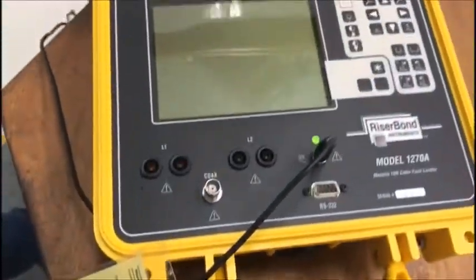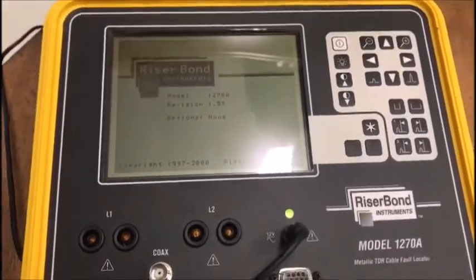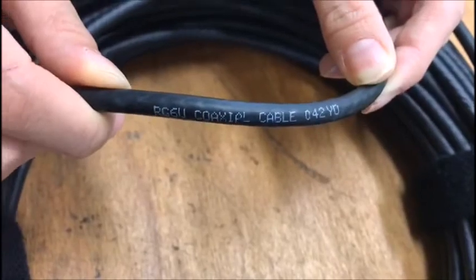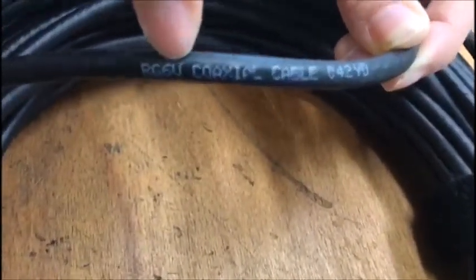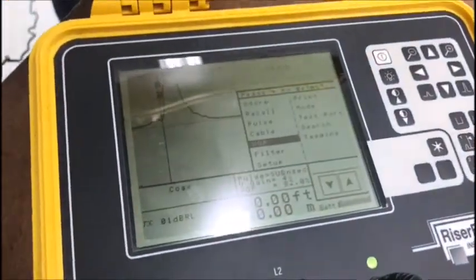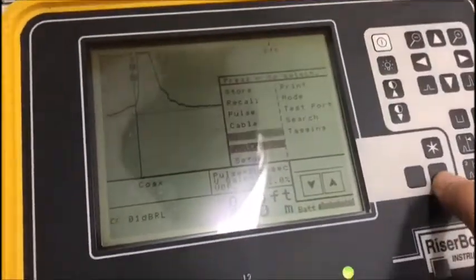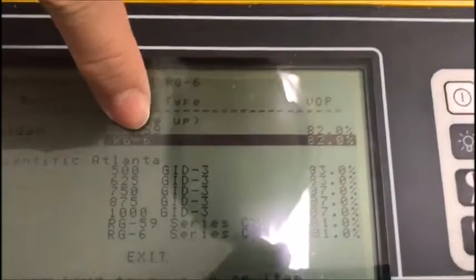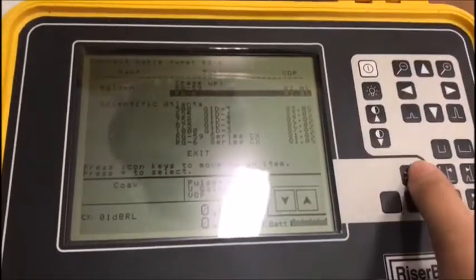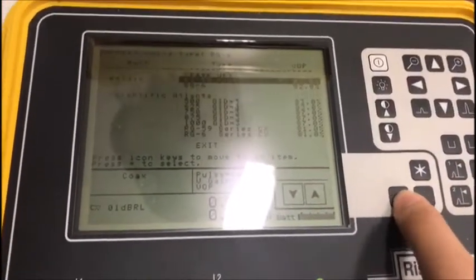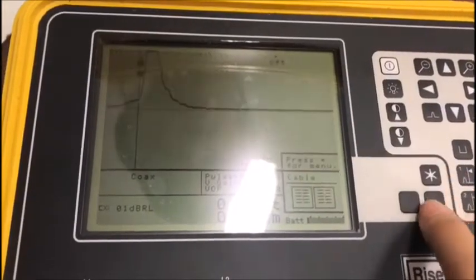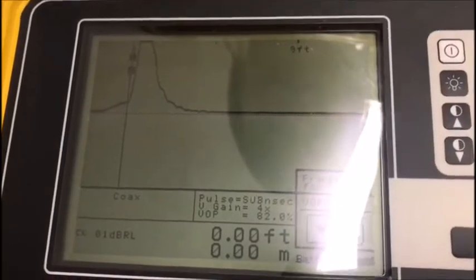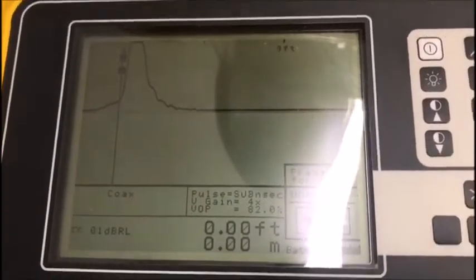So how do we do it? We first need to turn on the machine. And after that, you can go to the menu by pressing here. As you can see, this cable is RG6U. We come right here and you can see it listed. Check the cables — RG6 has 82% VOP, which is 82. So we can go back and set the VOP here. We can go up and down; it is already at 82, so we can leave it there. You can go back and plug in the cables.